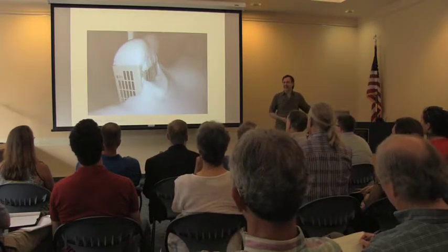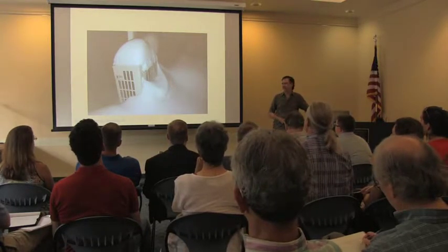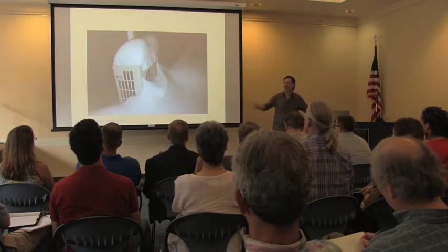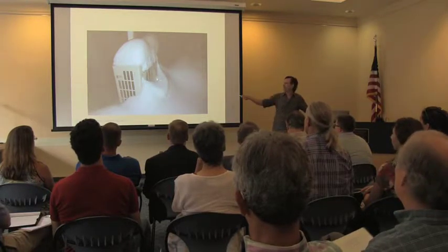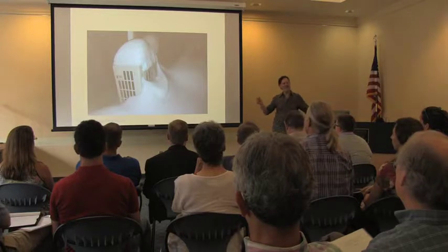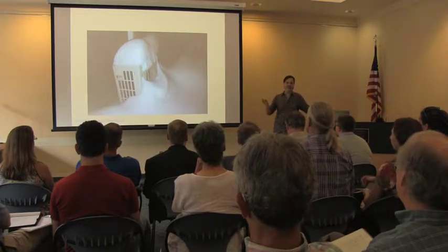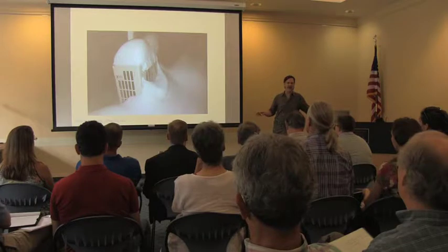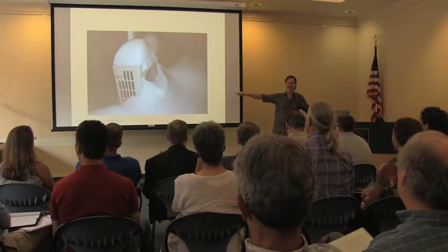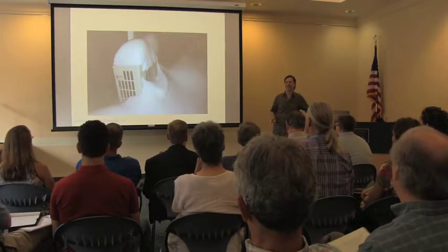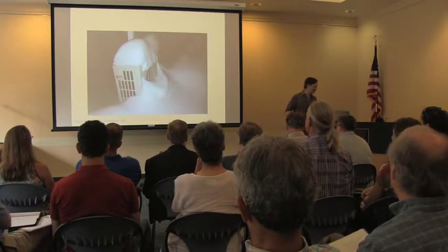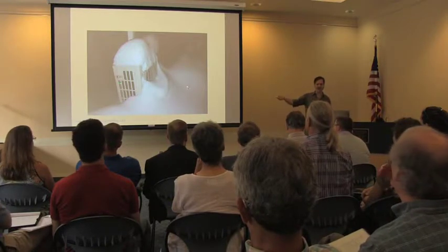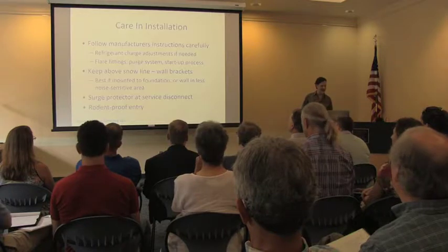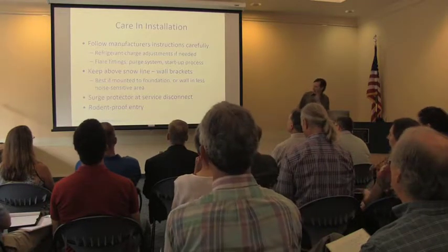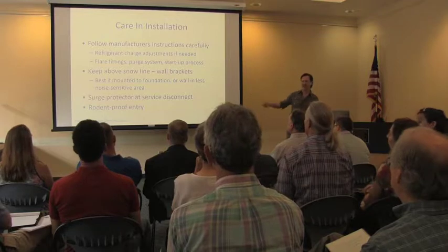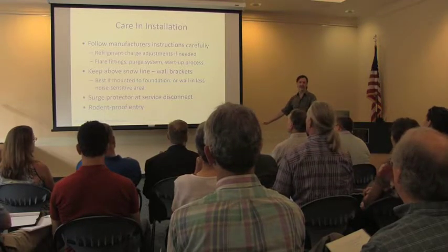The outdoor unit can't reject heat or absorb heat from the outside air if it's clogged up with snow and ice. Now, this unit didn't happen to be running, but it's something to watch out for in periods of really severe snowfall or if there's a power outage. Make sure that you clear the snow away from that unit before you turn the unit back on or before the power comes back on, because it's not going to be able to defrost in that kind of situation. But the basic idea is keep it above the snow line, 18 inches to 2 feet off the ground.